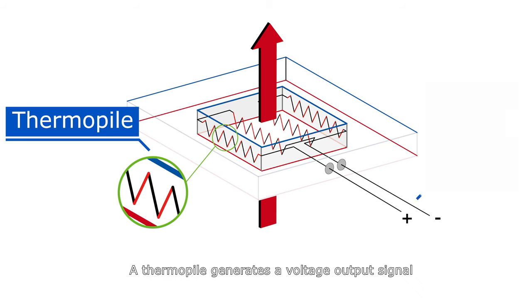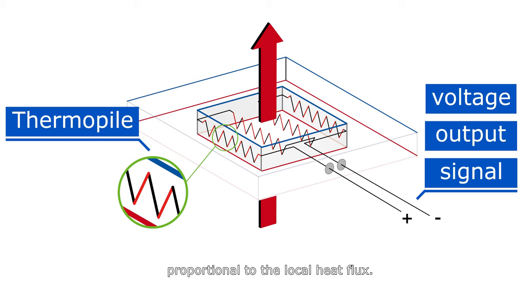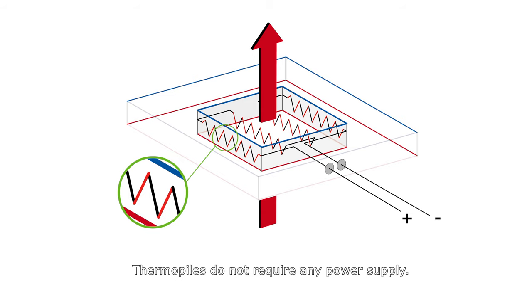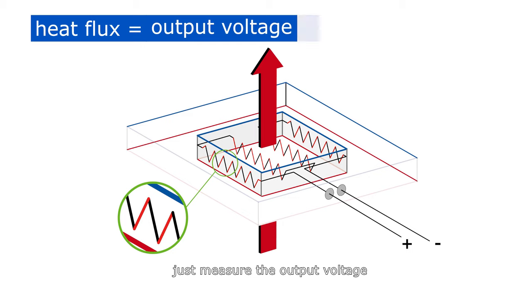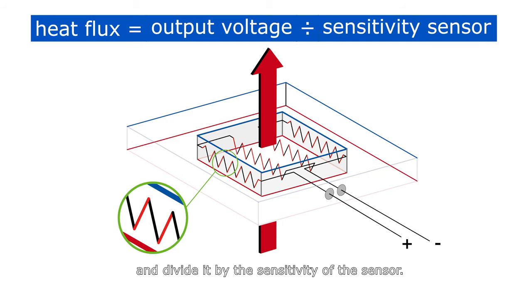A thermopile generates a voltage output signal proportional to the local heat flux. Thermopiles do not require any power supply. Calculating the heat flux is easy. Just measure the output voltage and divide it by the sensitivity of the sensor.